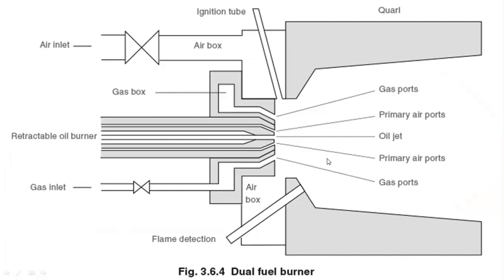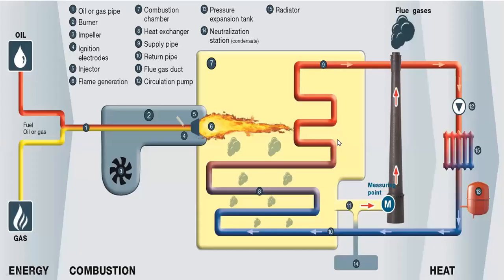This is a dual fuel burner: you have a retractable oil burner where oil is coming in and gas is coming through the annulus. The entire thing is a circular cross-section with oil and gas coming through, plus an ignition tube and flame detection mechanism. Air is coming through the air box, and you have oil jet primary air ports and gas ports. Continuous combustion takes place in this dual fuel burner.